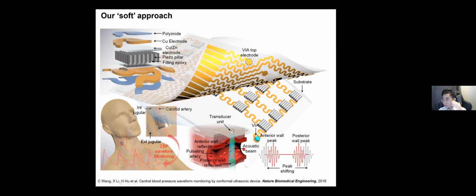The ultrasonic wave can penetrate through the skin and reach the blood vessel. We use it to pick up the vessel diameter in real time. When the ultrasonic wave meets the anterior wall of the blood vessel, it gets a signal reflection received by the transducer, producing a representative anterior wall peak.